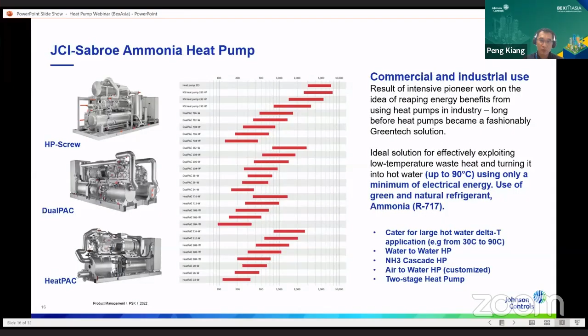And if you need a heat pump to do parallel cooling and heating at the same time, low temperature, 5, 10 degrees C, and high temperature to about 90 degrees C, you could even have a two-stage heat pump, which is a DualPAC in our sense, to do that kind of parallel cooling and heating at the same time. Now, let me share a couple of case studies, which will be more interesting for us to really understand how we can apply this, right? So I have a couple of case studies, which hopefully I will be able to illustrate through, right?